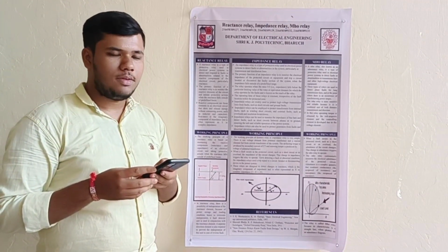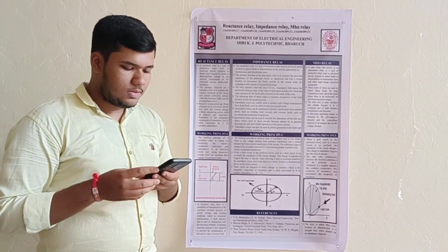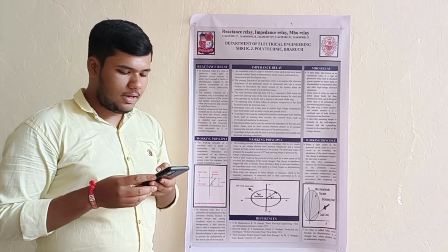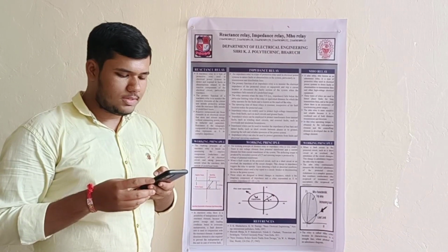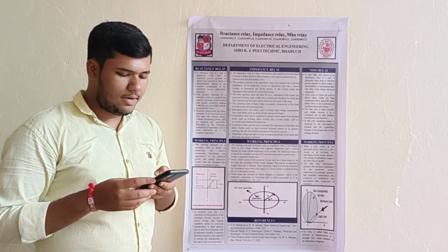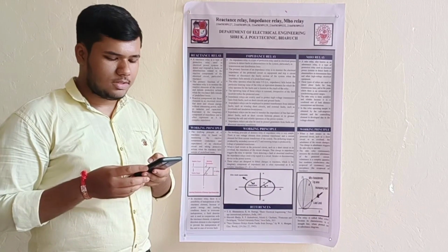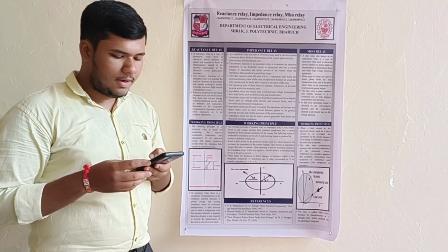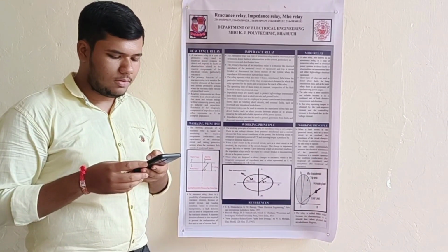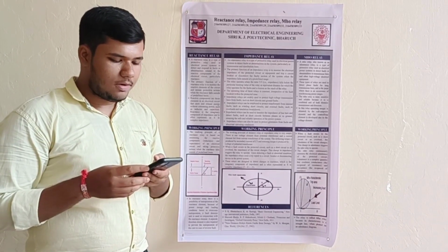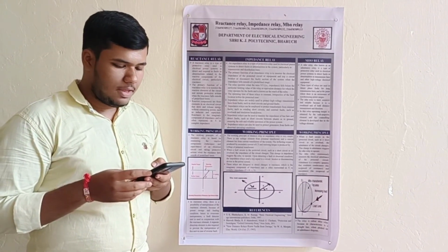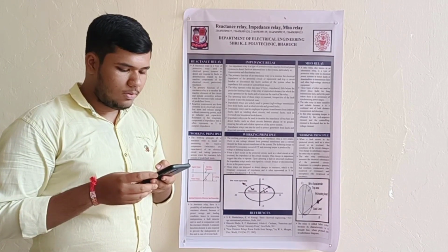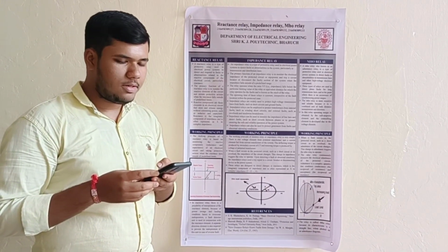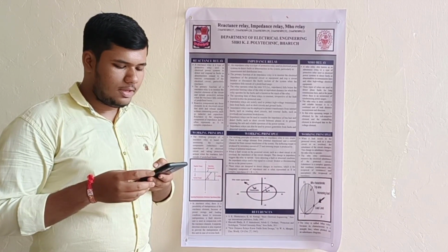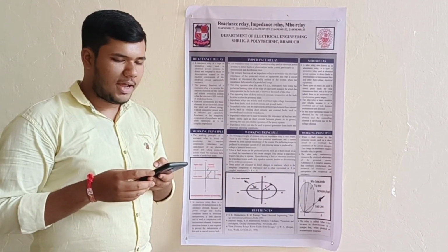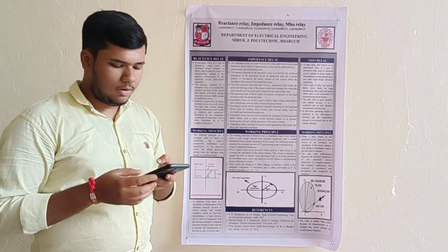Now the disadvantages of reactance relay. Now the first one is false tripping. Reactance relays can sometimes be prone to false tripping, where they detect a fault that does not actually exist. This can lead to unnecessary shutdown and disruption to the system. Now the second disadvantage is limited fault detection. Reactance relays are primarily designed to detect faults based on changes in reactance. They may not be as effective in detecting other types of faults such as short circuit or ground faults.